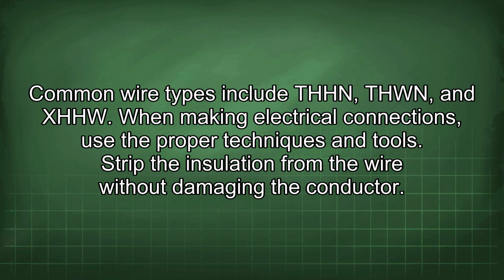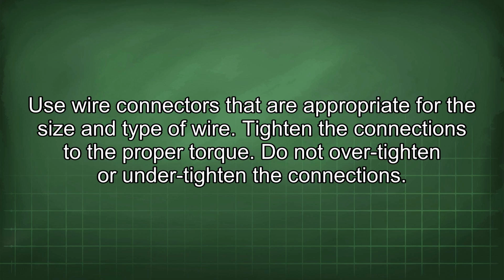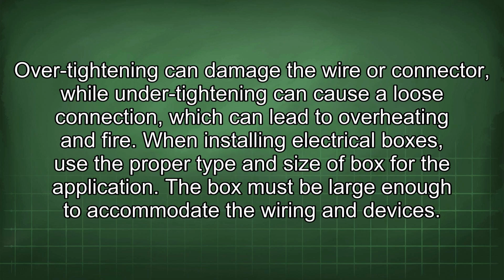When making electrical connections, use the proper techniques and tools. Strip the insulation from the wire without damaging the conductor. Use wire connectors that are appropriate for the size and type of wire. Tighten the connections to the proper torque. Do not over-tighten or under-tighten the connections. Over-tightening can damage the wire or connector, while under-tightening can cause a loose connection, which can lead to overheating and fire.